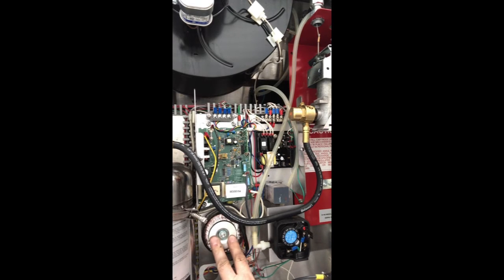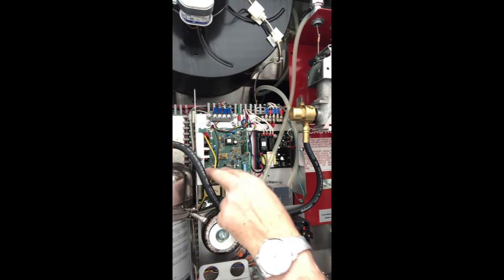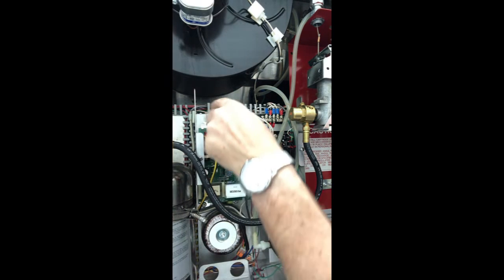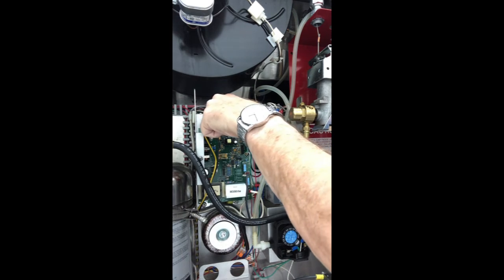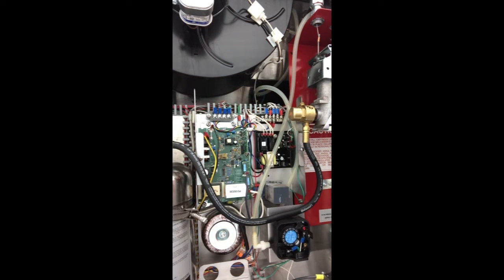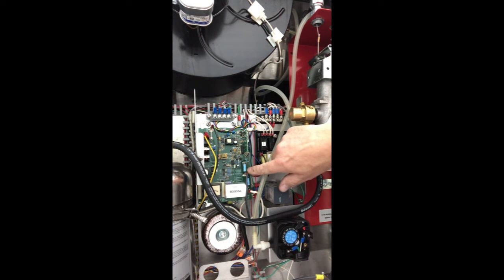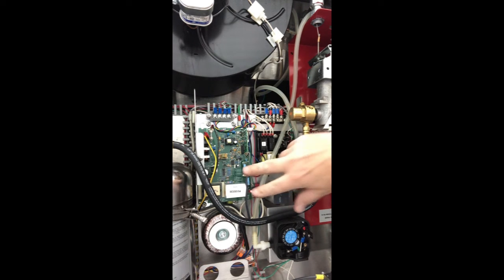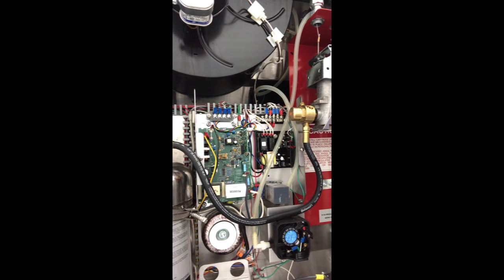We have our 110 volt transformer here. We're feeding our power in to here. We're feeding 208, 240 into this transformer. Coming out of the transformer, we're coming up with 110 volts, tying in right here to P1 and P2. Over here on this side, P3 and P4. These two are going out to our cell, out to our filter.